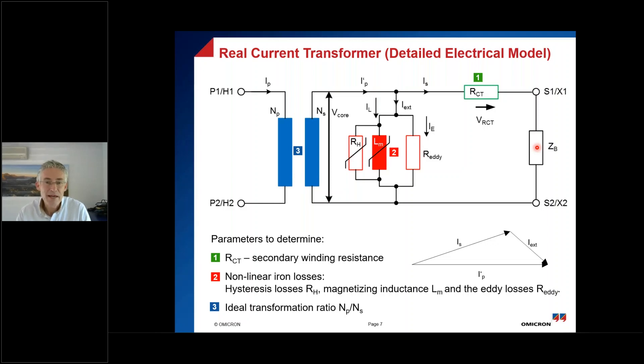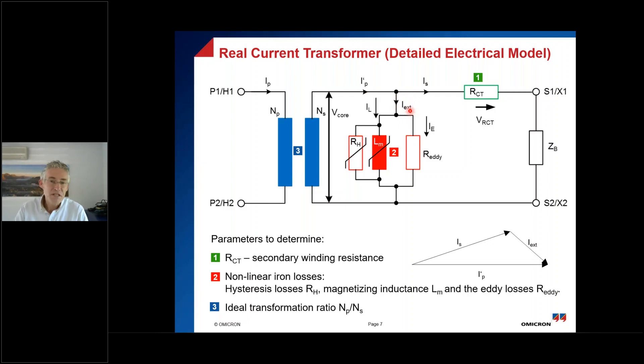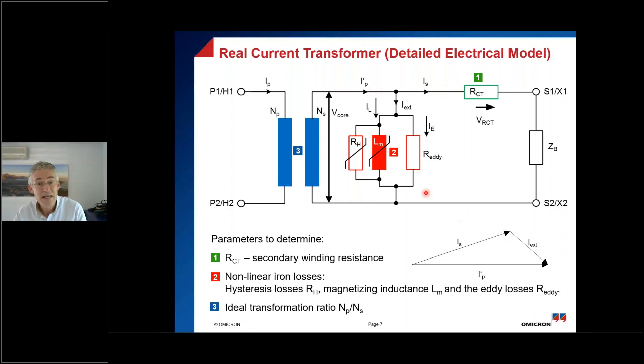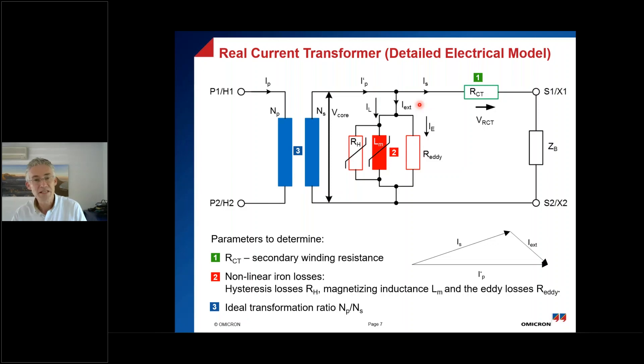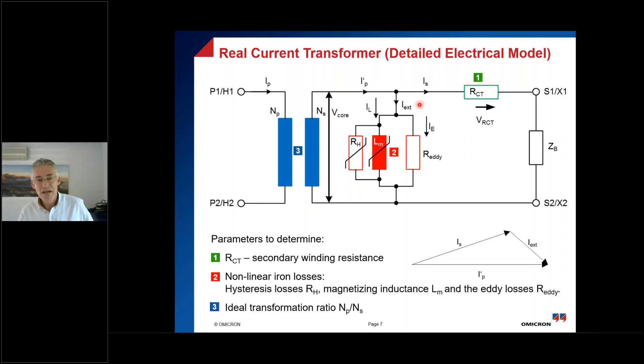Regarding the effect of load current: the excitation current is relatively constant across the load range, while the secondary current changes. This means that at low currents — say 10% of rated — the CT error is proportionally larger than at rated current. That is why it is important to test CTs at 5% and 10% current as well, and also why the standard allows for larger deviations at lower currents.